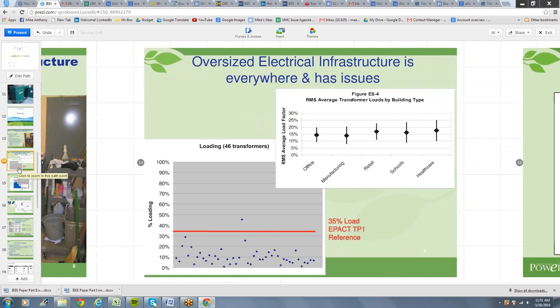A couple of things you really have to know. First of all, we're living in a world where transformers are much more lightly loaded than we think they are. That's a function of all these years. You've got code that's very conservative in terms of calculation, there's the design engineer allocating for future load growth, and then you're overlaying on top of that an evolution of the loads we're connecting to, actually smaller and smaller power supplies. What used to be a desktop computer at a couple hundred watts 10, 15 years ago, we're down to laptops with 15 or 20 watts. A huge difference in consumption.